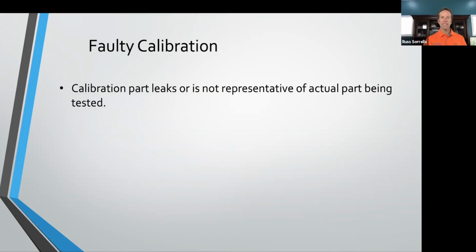All right, faulty calibration. Speaking specifically about pressure decay leak testing, we take a known good part, put it on the stand, the leak test fixturing, press auto calibration, and hit the buttons. The part seals up, and the instrumentation runs one test. That establishes our baseline, our no leak. So we've said this is a good part, and essentially it sets that pressure loss to zero in the instrumentation.